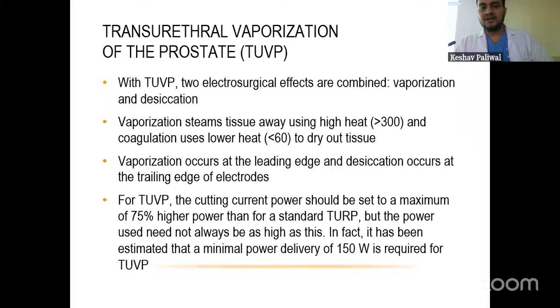For TUVP, the cutting current power should be set to a maximum of 75% higher power than for a standard TURP, but the power used need not always be as high as this. In fact, it has been estimated that a minimal power delivery of 150 watts is required for TUVP.